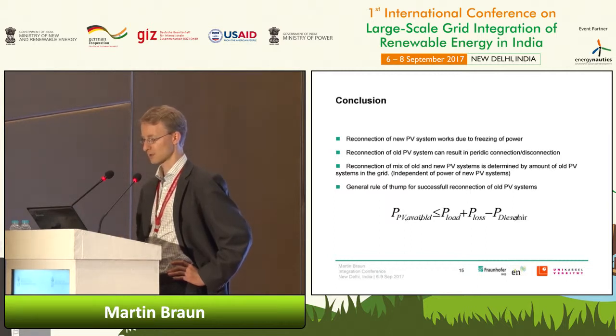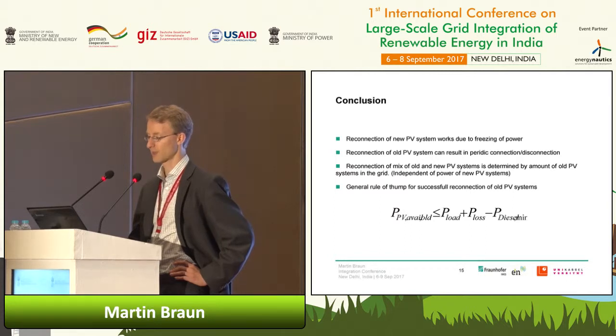What has been analyzed here as a general rule of thumb is that the available PV capacity of old PV systems should be smaller than the load of the system plus the losses minus the minimum diesel power. I think this is quite logical. This is a little rule of thumb, hopefully not necessary to be applied here in Indian or other contexts.